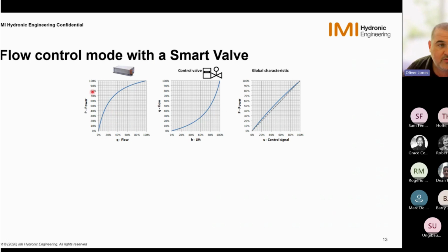We can see we still have our terminal unit with its non-linearity, so we can see that the physics are exactly the same. But this time we have a valve that, according to a certain signal, will position itself to the lift. So these two are related linearly, and it will give you a flow according to a curve that we choose to be equal percentage, so that it compensates for the curve of the terminal unit. So this time we can see we've simplified the process. There's no longer the actuator curve that's playing a part into it, or the hydronic instabilities or delta P variations that are playing into this, because we've condensed that with the control valve, with what it's doing by monitoring the flow across itself.